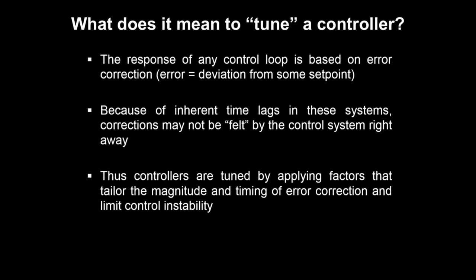So you might hear that these controllers or control loops are able to be tuned. So what does that mean, and why might we want to tune a PID loop? Well, there's different elements, as we'll see, within a PID loop, and tuning those individually will change the control response that we have. It can make it more robust, faster, or less prone to instability. And the reason that we need to tune that is because each control loop is really specific to the process variables in place, to the different feedback lags that we may have. And even though we may see advertised controllers that are factory tuned, we really need to be able to tune the system to the specific application and distribution and infrastructure that it belongs to.